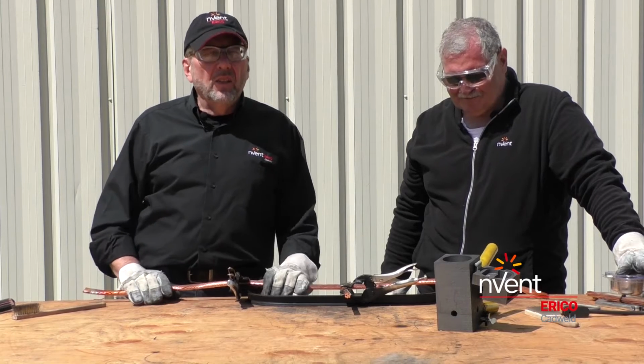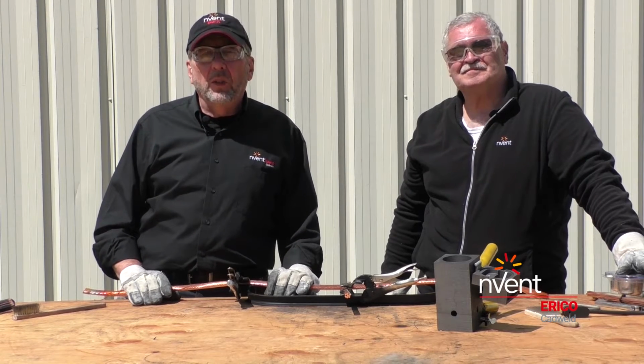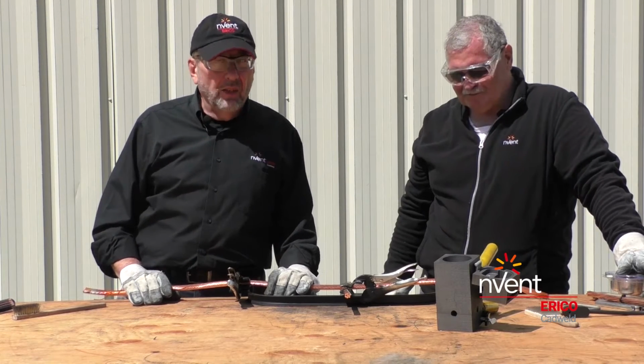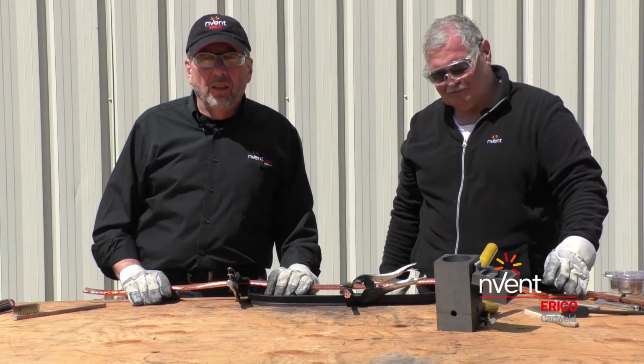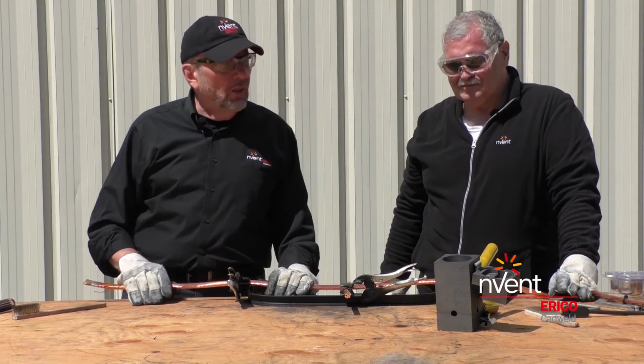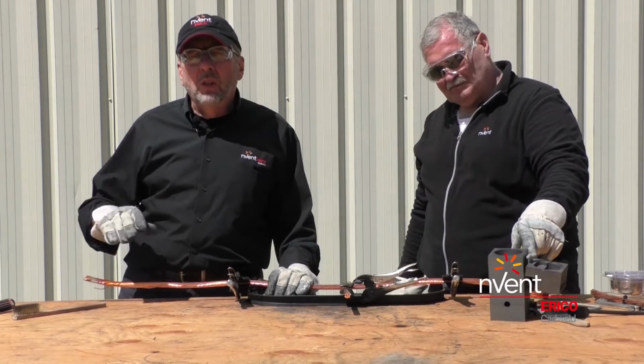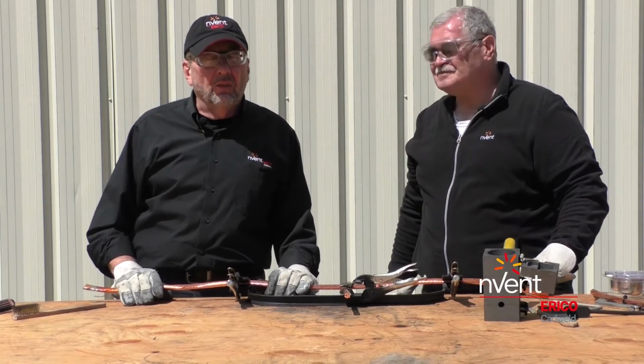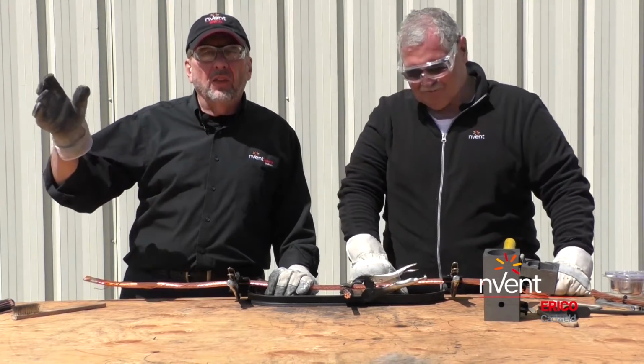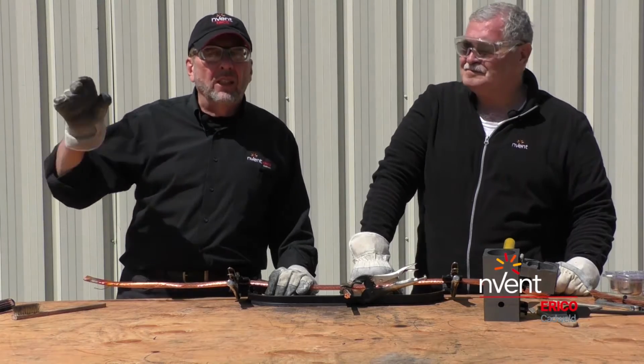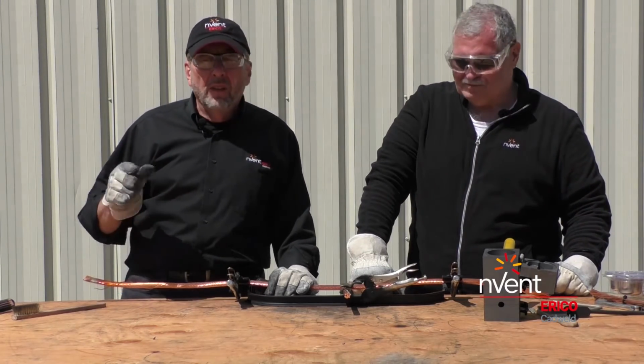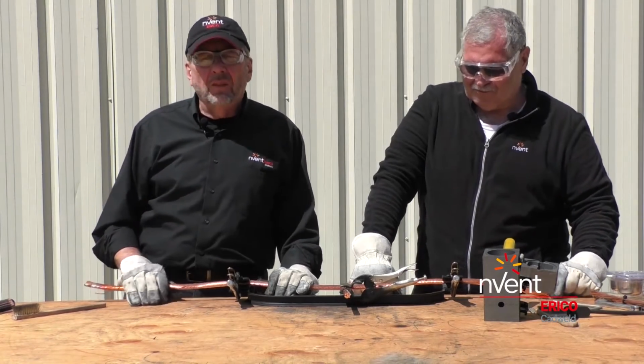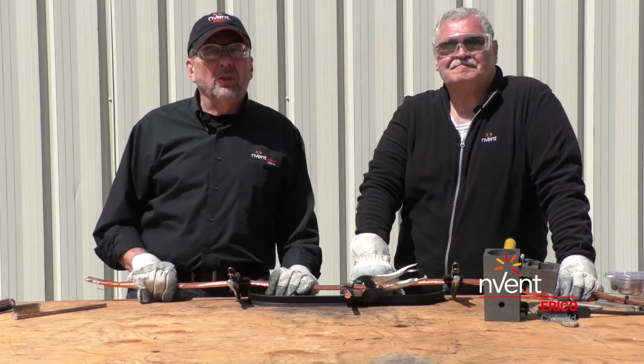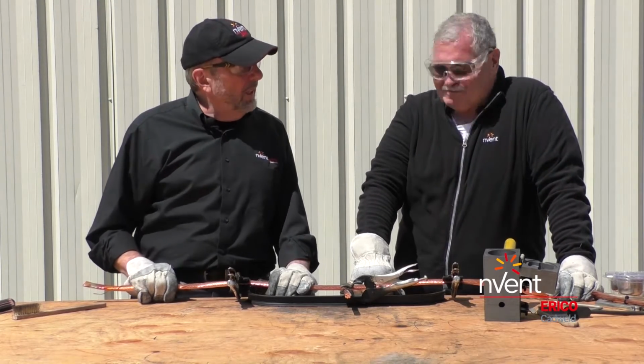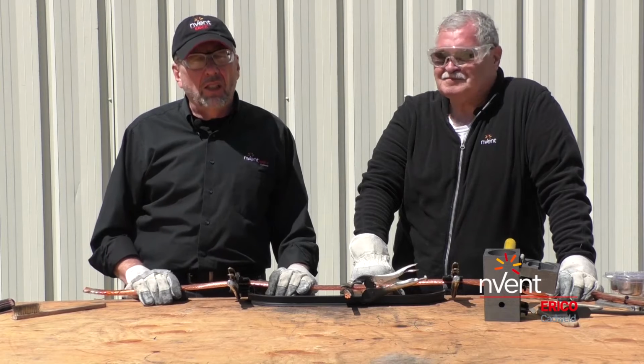The next phase of building our ground grid will be cable-to-cable connections. These types of connections are either used to extend cable or to make connections to the grid forming pigtails that bring leads into ground structures. That happens in all kinds of commercial and industrial facilities, and it's very common at substations.